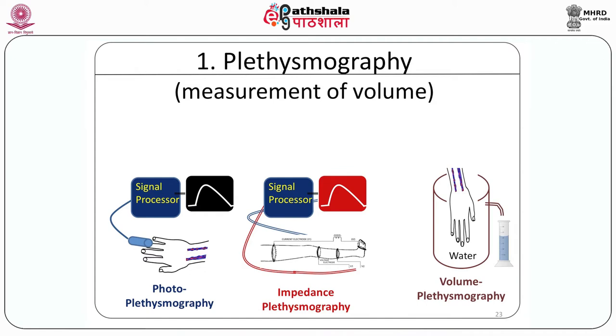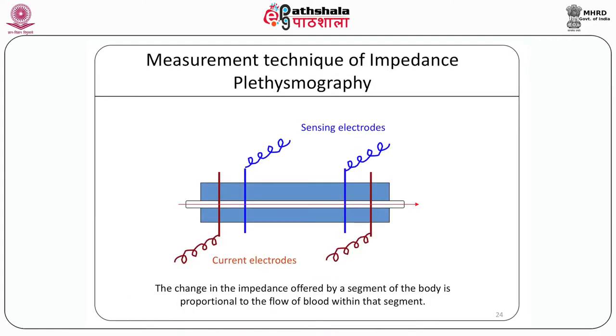The volume plethysmography by using water or air displacement is a standard teaching tool for students of physiology. The impedance plethysmography technique uses a very small, non-perceivable current and is entirely safe. This is injected into the body at a very high frequency in the range of 50 to 100 kHz. Blood is a very good conductor of current and is the only thing which is changing in the area. Thus, the change in impedance offered by a segment of the body is proportional to the flow of blood within that segment.